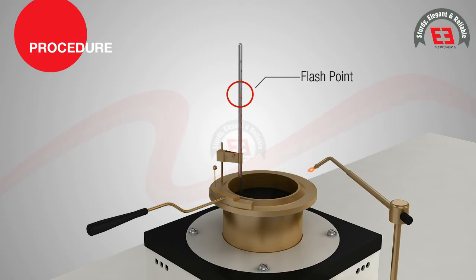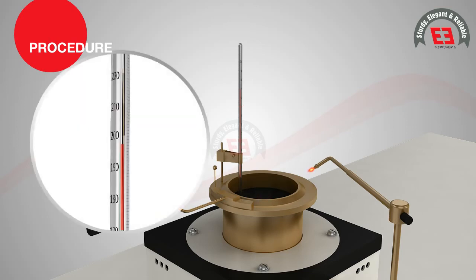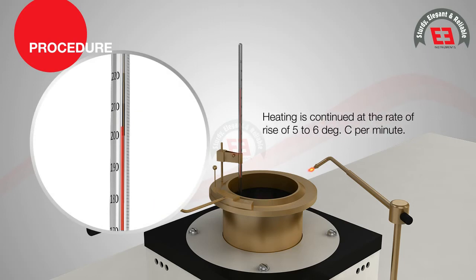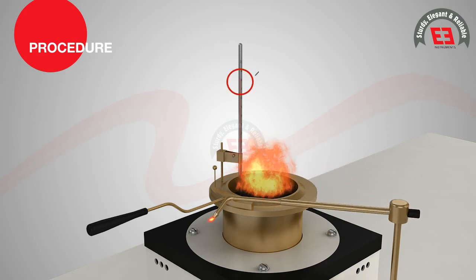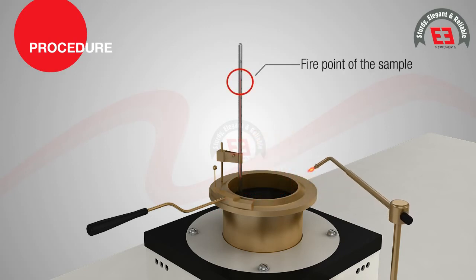After determining the flash point, heating is continued at the rate of rise of 5 to 6 degrees Celsius per minute. Application of the test flame is continued, and when the sample ignites for a minimum period of 5 seconds, the temperature indicated on the thermometer is noted as the fire point of the sample.